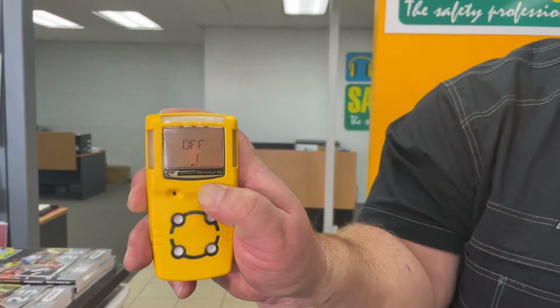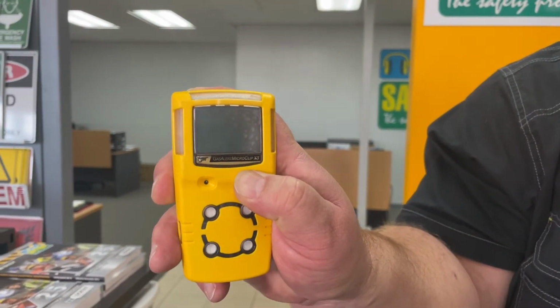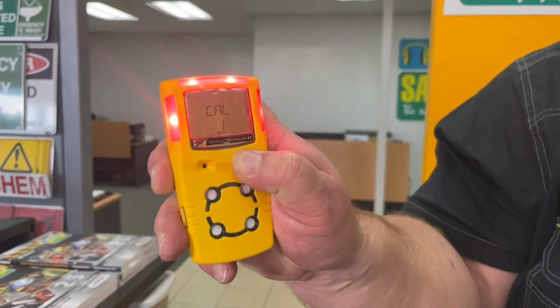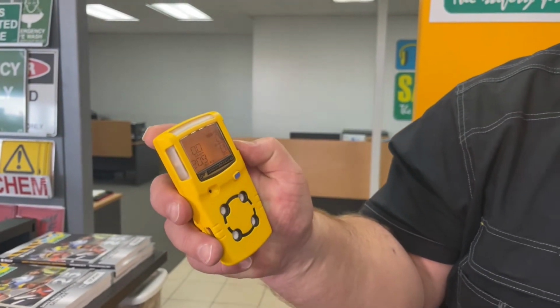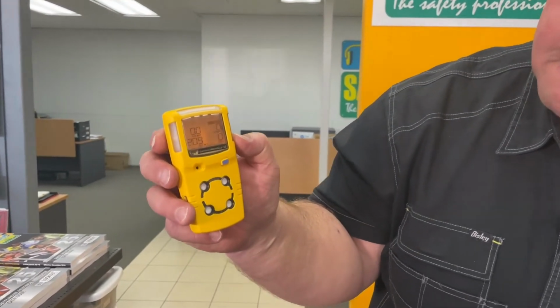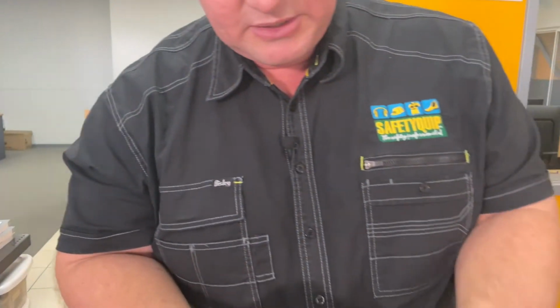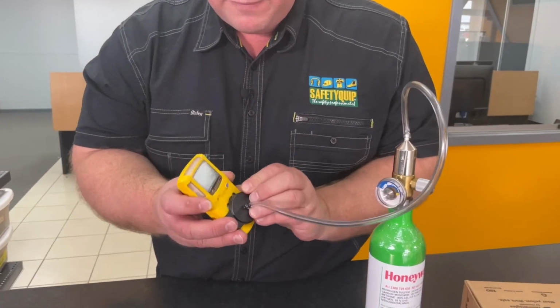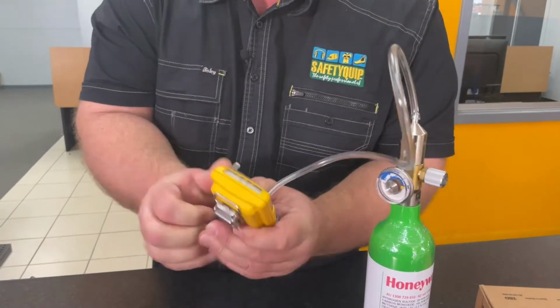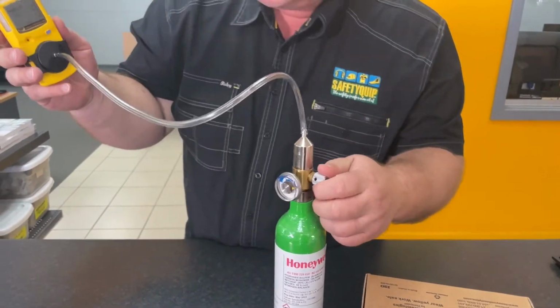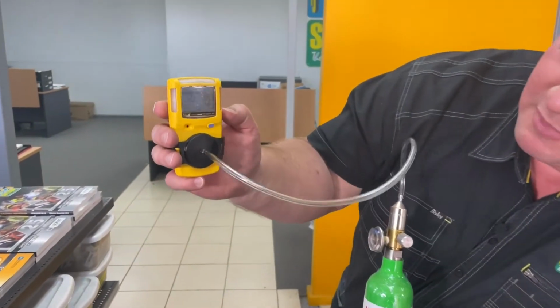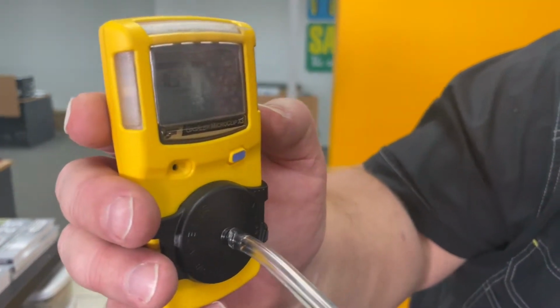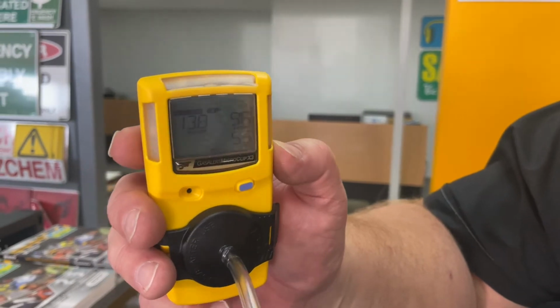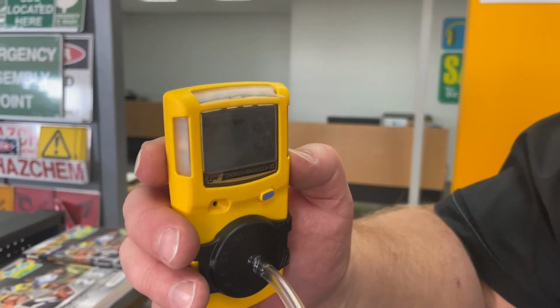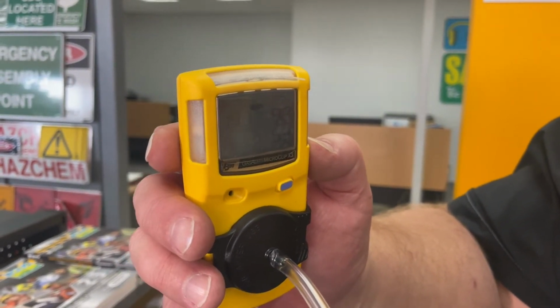So let's do that. So I'll press and hold. That's switching the unit off. I'm still holding it. Now it's counting down the calibration process. It's zeroing the sensors. And now it's telling us to apply gas. So I'm going to fit that test cap on the front, and I'm going to dispense some gas in there. So we'll see in a moment that it's recognising gas on that screen, and it's doing the span now.